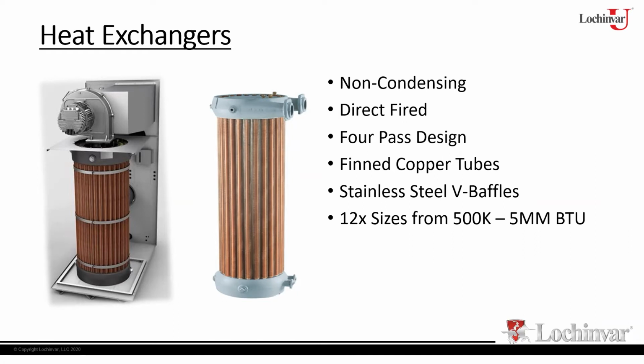They go over to the assembly line, where we have an assembler who will basically start with the bottom header, put the appropriate number of tubes into position, put on the top header, and then basically roll or press each one of those copper tubes into the header using the rolling tool. Again, no gaskets. You eliminate the gaskets, we eliminate the leaks at that point. So this is a long process because you can have anywhere from 20 to 60 tubes depending upon the heat exchanger. So it does take a while to actually build this heat exchanger.